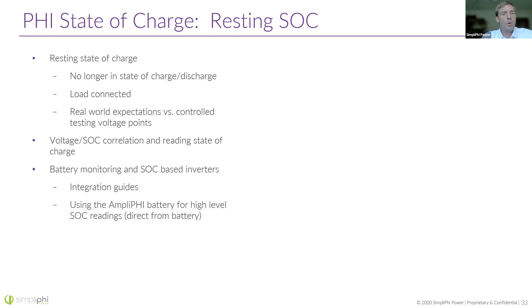Okay, as mentioned before, this is the state of charge for a battery. This is a graph of the state of charge for a battery under load. When the battery is discharging at a rate of C/2, you have a lower voltage even for the same state of charge. So if you're at 51 volts but discharging rapidly, you could still be at 70% state of charge. If I can put my mouse there, you're a little under 70% state of charge, but you're discharging at a very high rate. But if you're at 51 volts, you also might have 80% state of charge, or even 85%, 83, something like that, depending on how quickly the battery is being drawn. So this is the state of charge for a discharging battery.